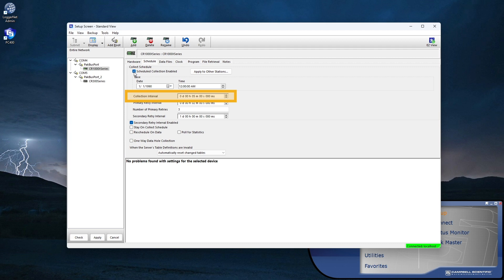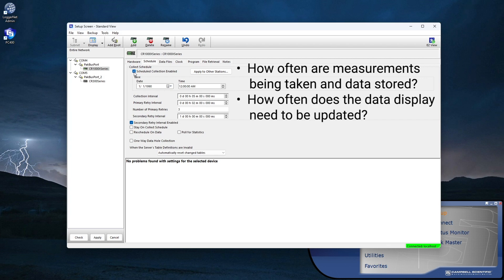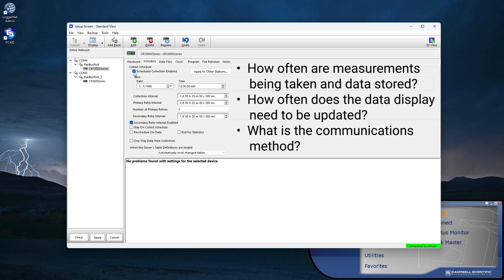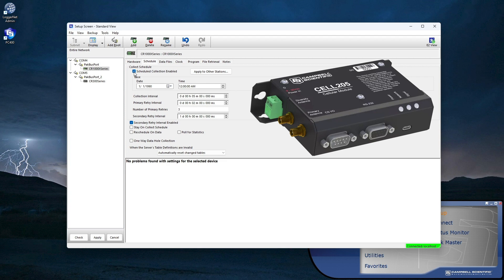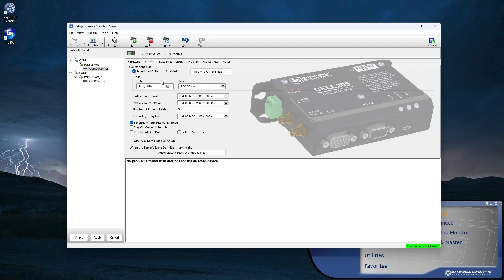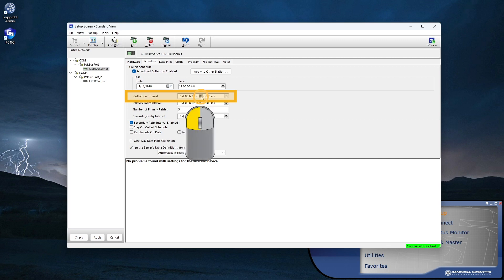There are several things to consider: how often are the measurements being taken and data stored, how often does the data display need to be updated, and what is the communications method? When an expensive communications link like a cellular modem is used, collecting data and updating RTMC screens will likely occur less frequently than when a direct connection is used. For this tutorial, I'm using a direct connection and want real-time values, so I'll set the Scheduled Collection interval to one second.